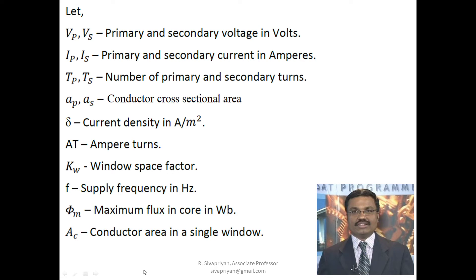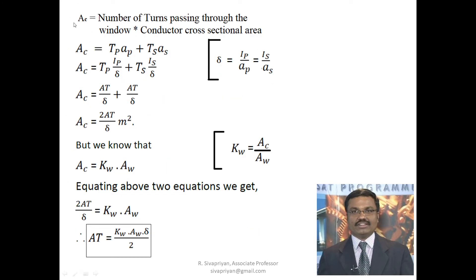Kw is called the window space factor — it is the ratio of conductor area in a window to the area of the window, so Kw = Ac/Aw. The supply frequency is f in hertz, φm is the maximum value of flux in the core in Weber, and Ac is the conductor area in a single window. Ac is calculated as: number of turns passing through the window multiplied by the conductor cross-sectional area. We take only one window even if the transformer has multiple windows.